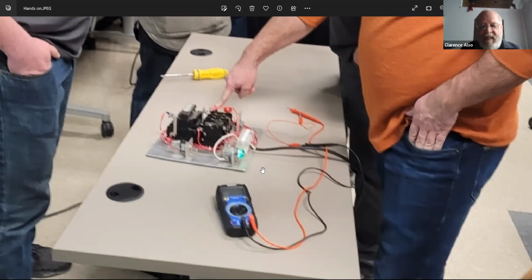After he does that, then he can maybe test his meter, doing it with a red probe. If you remember that circuit for the motor starter, it kind of plugged into a 120-volt wall. Terminal number 1 was where the hot was, number 2 was where the neutral was at. So, where would you put, if you wanted to test that meter to see if it's working right, with that red probe, since you've already clipped the black alligator clip through to number 2, and you just want to troubleshoot with one hand, where would you put that probe in the circuit? Do you recall that circuit?